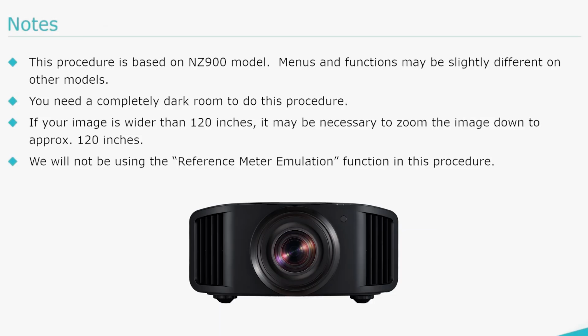Just one note, this procedure is based on the NZ900 model. So if you have maybe an NZ500 or 700, it might be a little different for that. You do need a completely dark room to do this procedure, so make sure the room can be turned completely dark as you're doing this. If you're doing a very large image, I suggest you zoom the image down to a smaller size to do the calibration. And then once you're done, you can bring the size back out.